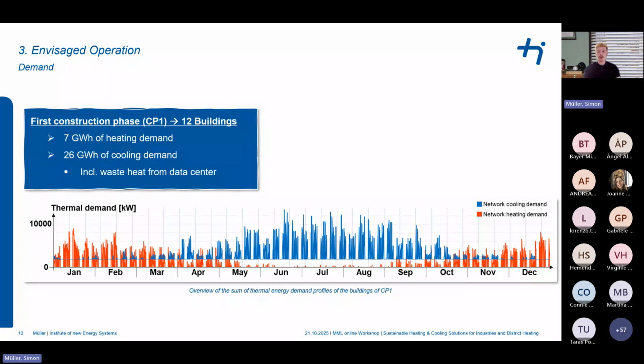There is something that can be called balanced demand. This is the case when one building connected to the network has a heating demand and another building, because of its function or utilization, has a cooling demand at the same time. So at the end of October, for example, the data center with its cooling demand will eject heat into the network via heat exchanger, and on the other end of the network, some office buildings with heating demands will extract heat via heat pumps. So instead of fulfilling the demands separately, the demands are balanced in the TSN.